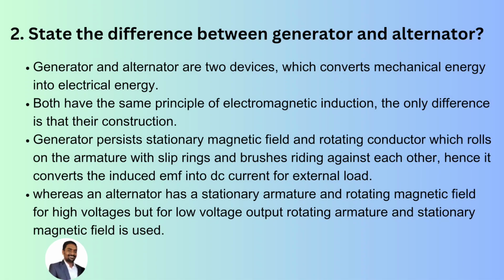State the difference between a generator and an alternator. Generator and alternator are two devices which convert mechanical energy into electrical energy. Both have the same principle of electromagnetic induction. The only difference is their construction. A generator has a stationary magnetic field and rotating conductors on the armature, with slip rings and brushes riding against each other. Hence it converts the induced EMF into DC current for the external load, whereas an alternator has a stationary armature and rotating magnetic field for high voltages, but for low voltage output a rotating armature and stationary magnetic field is used.